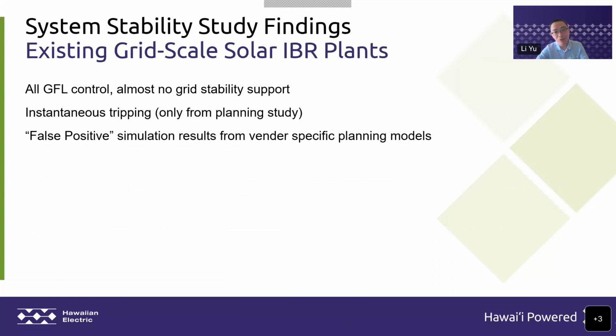After all this about the DER findings, we also see some risk regarding the existing grid-scale solar IBR plants. So far, we have around 180 megawatts of contract capacity for grid-scale solar IBR plants in our Oahu system. They are transmission-level interconnected and sub-transmission-level interconnected. All of them are GFL control, and for all of them we have the vendor OEM inverter PSS/E model and PSCAD model.